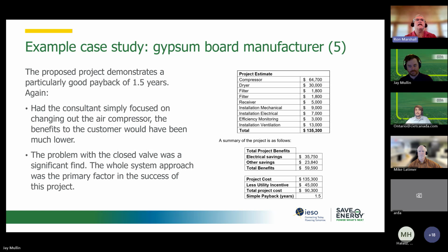This project had a payback of 1.5 years, including a utility incentive of $45,000. So if the consultant only focused on changing out the compressor, a lot of those other benefits would have been missed, right? So it's important to have a full audit done, and the problem of the closed valve would be missed as well if they just put pressure loggers right in the compressor room, like so many auditors do.